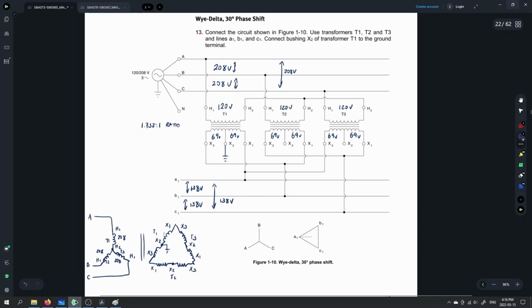For transformer number 1, X1 feeds the A phase here. X3 is tied into B, so there's A to B. We can see X1 of transformer 2 also ties into B, and X3 of transformer 2 goes to C, so this feeds C.